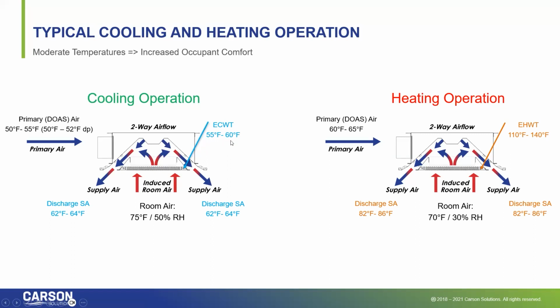And in cooling, we are typically feeding that hydronic coil with elevated chilled water, and in heating, moderate warm water. And as that room air then mixes with the fresh air, we get supply discharge out to the space. In cooling, somewhere between 62 and 64 degrees, and then heating somewhere between 82 and 85 degrees.